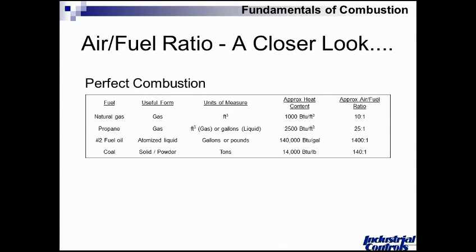The magical thing you'll see is that the combustion air requirements are really a function of the BTU content of the fuel. When we see about 2,500 BTUs a cubic foot for propane, amazingly, our fuel air ratio has changed. Instead of needing 10 cubic feet of air for one cubic foot of gas, we now need two and a half times that because that's relating back to our heat content of the fuel. When you think about, for example, a boiler which has one forced draft fan developing the air volume for combustion process, we don't change the blower size based on which fuel we're firing. We change the volume of fuel delivered so we can use the very same fan. Under propane firing conditions, we have a much lower volumetric flow of fuel required to release the full amount of heat than when firing natural gas.